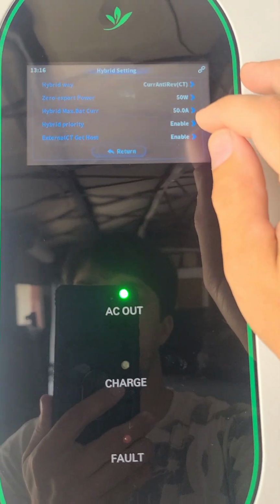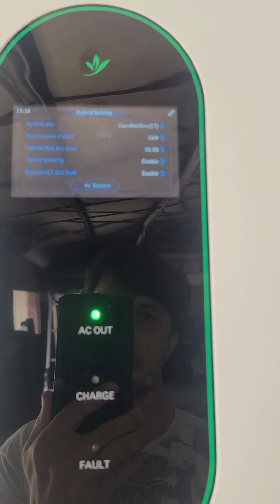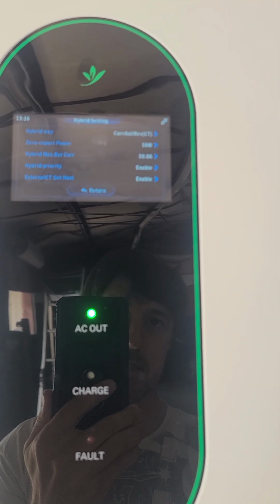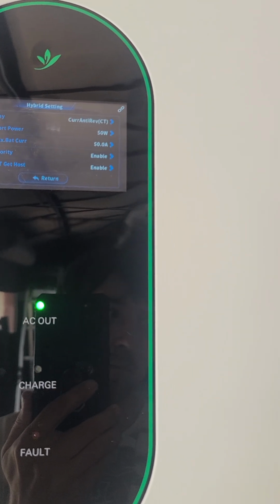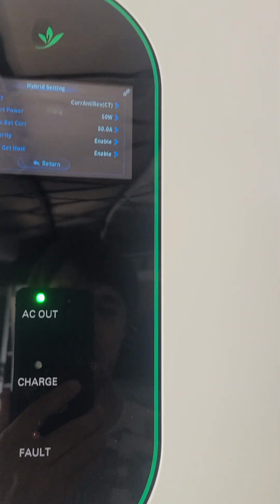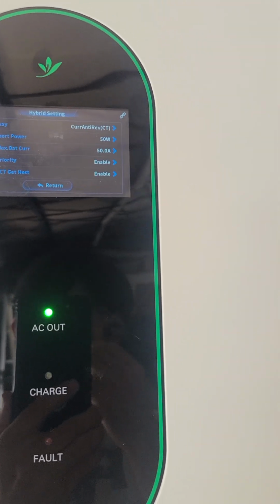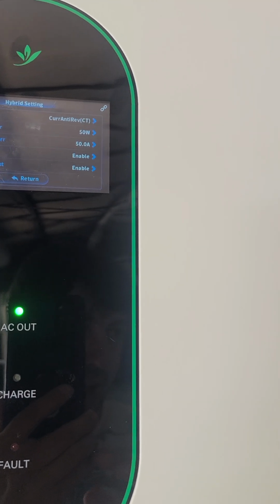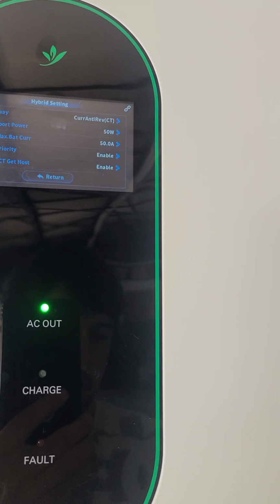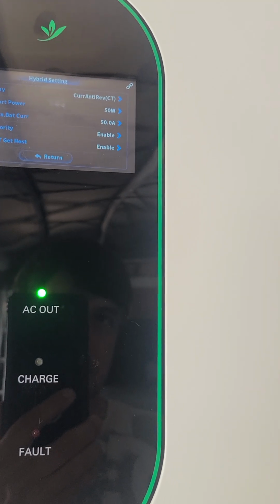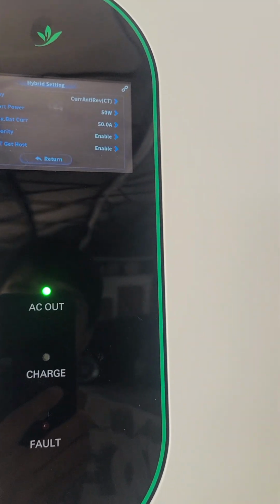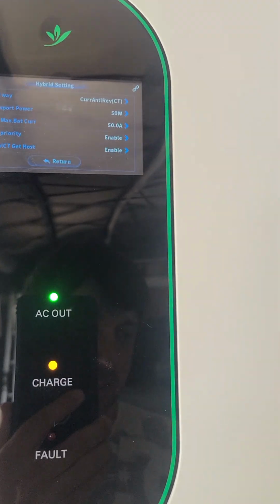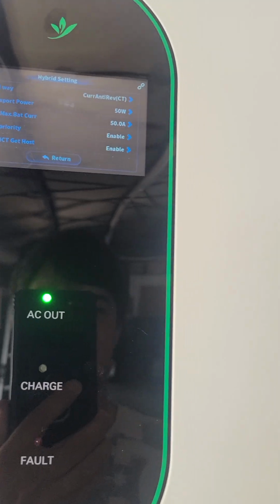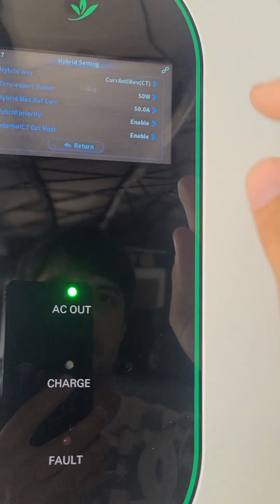Our hybrid priority, we do enable that, because if you do not, then it's gonna send the PV to the batteries instead of the utility, basically. It just makes weird things happen that don't work the way you want. You want your solar to charge your batteries and send to the utility. So you want to send your solar to the utility, and what you're not using on the utility, you charge your batteries. And that's what the hybrid priority means. I guess turning that off would send it to the batteries and then not to the utility, and it would use the batteries for the utility. But you have to get to the setting that I'm about to show you for that to even work. And of course you need the external CT get host enabled to use the CTs.